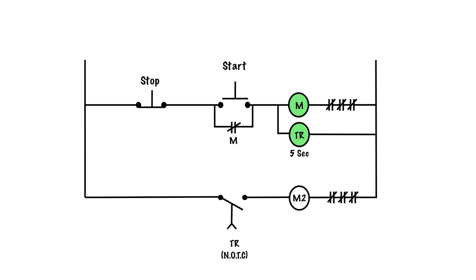Now we notice down here we have a normally open time-to-close contact. They stay open for 5 seconds. So I press this button, this energizes, this energizes, and then 5 seconds later, this normally open time-to-close contact will close, and M2 will start.